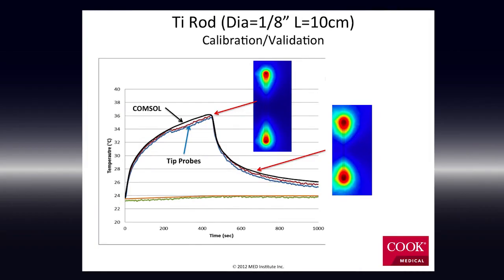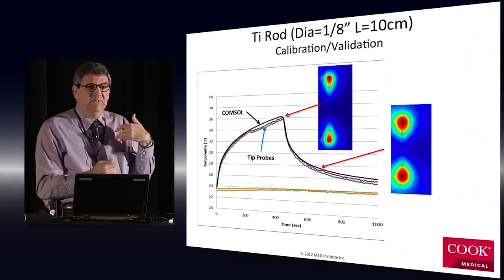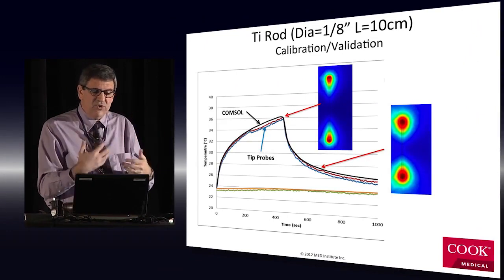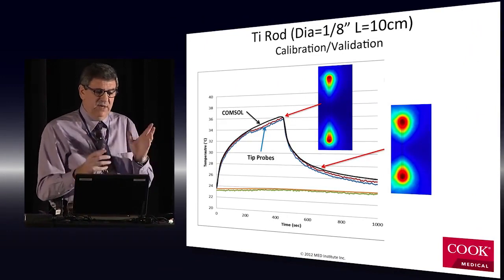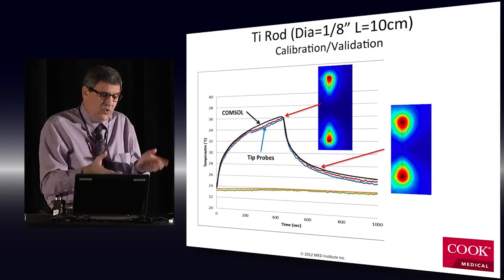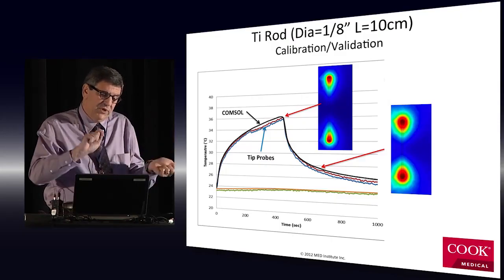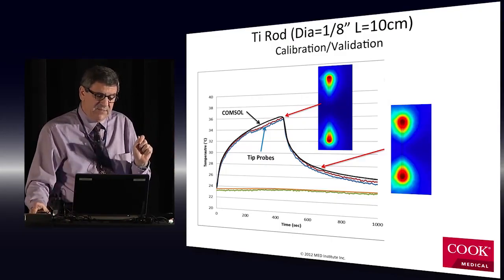And what we're doing here is part calibration. I basically don't know what voltage to apply to my coil. It's not something the manufacturer will give you. We don't know all the electronics and the RF amplifiers and everything. So we have this idealized coil. We have to apply voltage to a port. So we tune the voltage until I hit this maximum temperature.